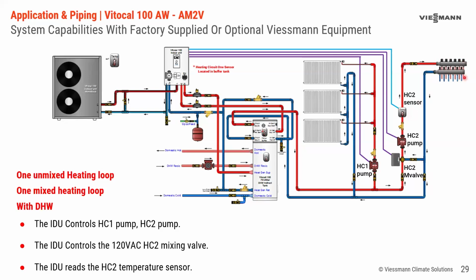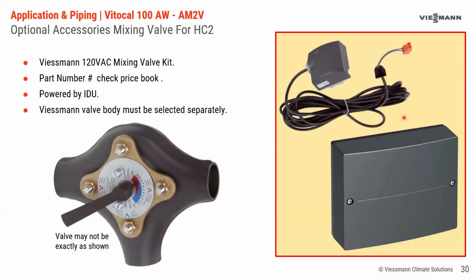If this was radiant cooling, we would have to add some extra controls or make sure that the set point was higher than whatever the dew point was. And normally we would put some humidity control, which would look at the dew point and say, hey, we're going to turn off the heat pump, when we don't want the floor sweating, that kind of thing. So the valve in the Viessmann kit is the 120 volt valve.